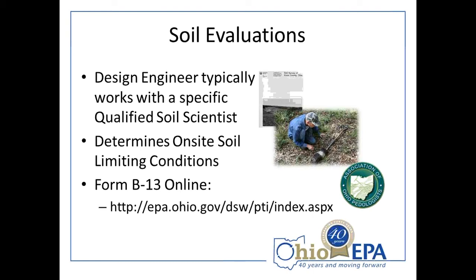Typically an engineering firm you select will have qualified soil scientists they work with. Years ago, Ohio EPA relied on post-World War II county soil surveys, which were estimations of soil types in an area. Ohio EPA has found these reports may not be accurate for your particular site. It is always best to have actual soil samples taken and confirm the soil types at your site so that an appropriate system can be designed.